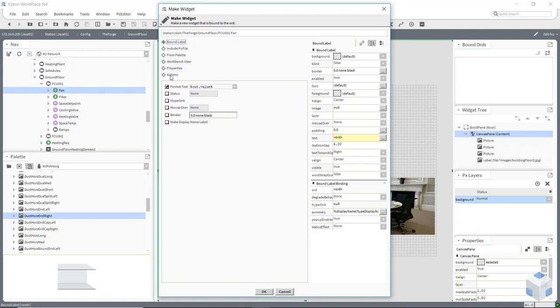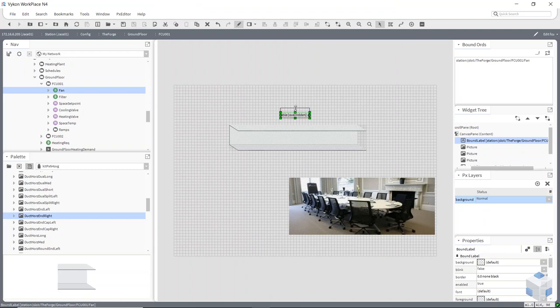When I bring the fan on, the widget wizard comes up asking how I want it represented on my canvas. These are all the different options. I can make it a label and include a PX file from palette, workbench view, properties, or actions. If you want a label, go for Bound Label. The format by default when you first use N4 shows a full stop in the middle of two percentage marks. It brings on the whole out slot of the component, showing the state of the value — enable — and the status, which is overridden.